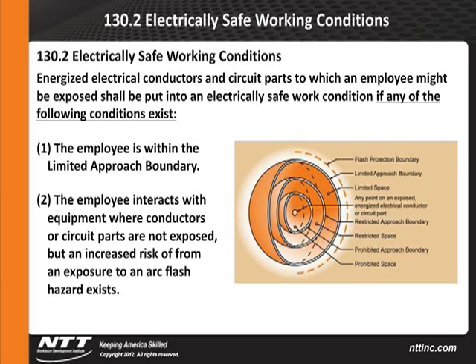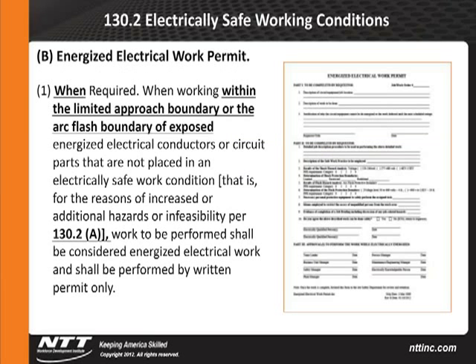It goes on to say that if we're going to have to work on something hot, we also need to use something called an energized work permit. When working within the limited approach boundary or the arc flash boundary of exposed energized electrical conductors or circuit parts that are not placed in an electrically safe work condition, for reasons of increased or additional hazards, the work to be performed shall be considered energized electrical work and shall be performed by written permit only. Again, another significant change, because I might have a 480-volt system. The limited approach boundary was 3 foot 6 inches, and I only needed that permit in that range. What if the arc flash boundary is now 9 feet or 15 feet? This is adding more requirements.